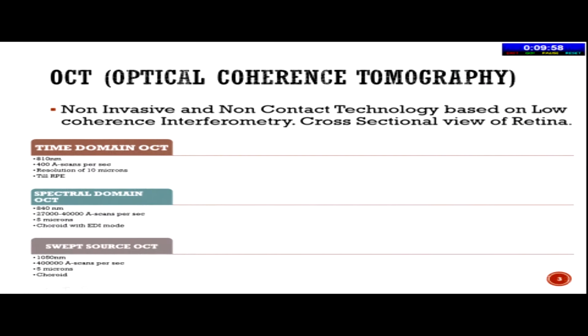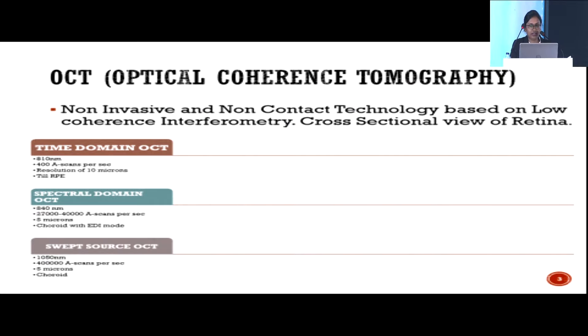OCT is a non-invasive, non-contact technology based on low-coherence interferometry that produces a cross-sectional view of the retina. Earlier, time domain OCT used 810 nanometers of laser light and was very slow, producing only 400 A-scans per second, with a resolution of 10 microns, scanning up to the retinal pigment epithelium.